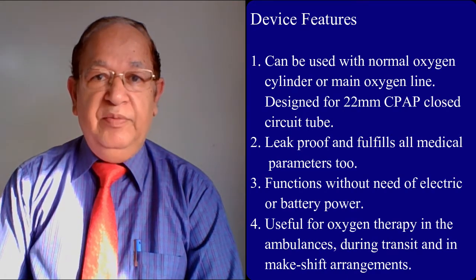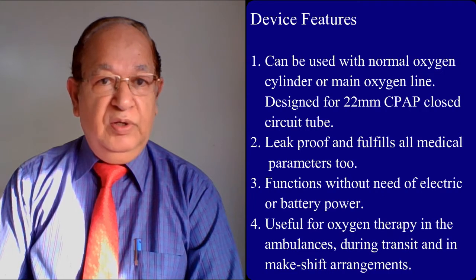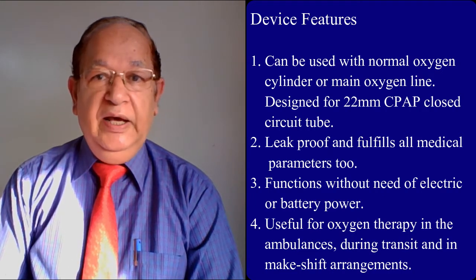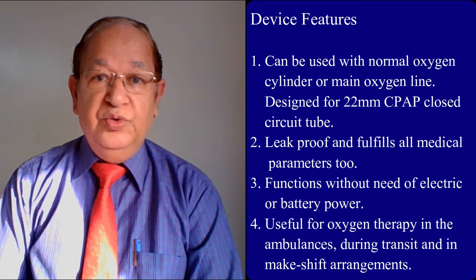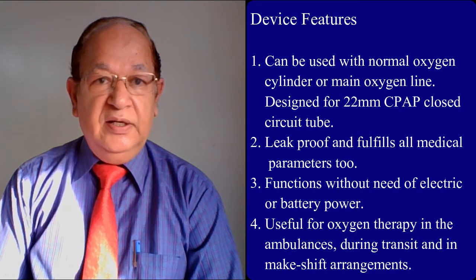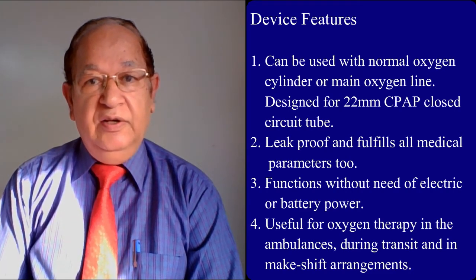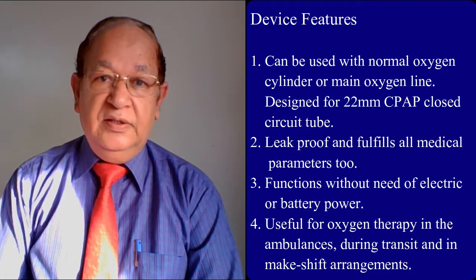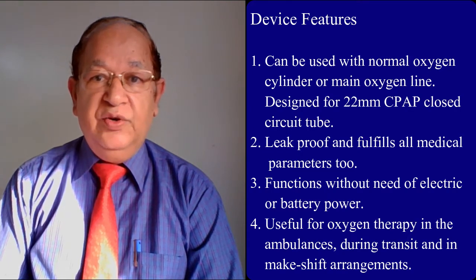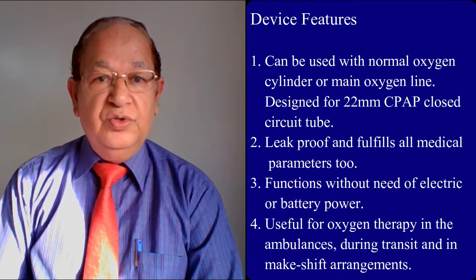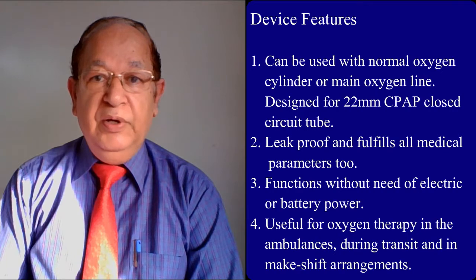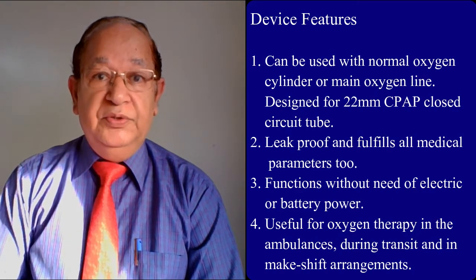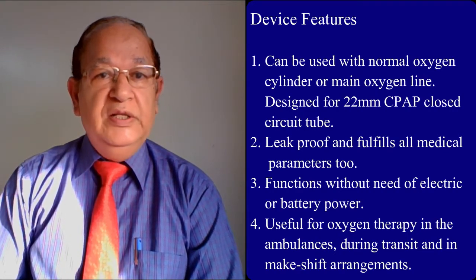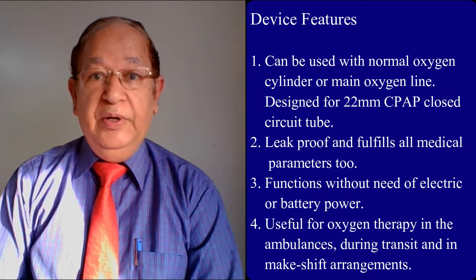The device, named Jeevan Vayu, has multiple features, namely, number one, this potentially life-saving device can be used with a normal oxygen cylinder or main oxygen line at an accelerated flow rate. The device is designed for a 22 mm CPAP closed circuit tube and can be customized. Number two, the device is leak-proof and fulfills all the medically required parameters too.